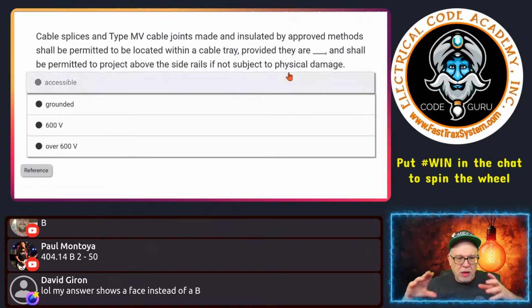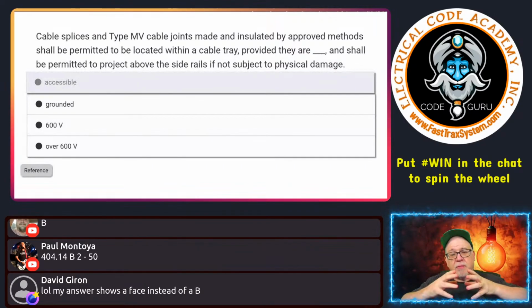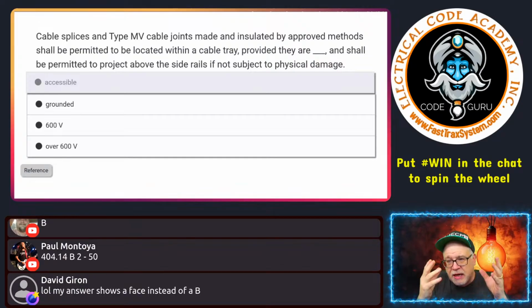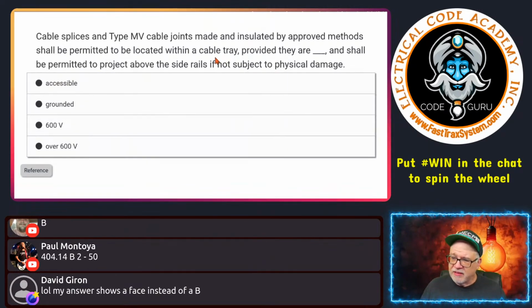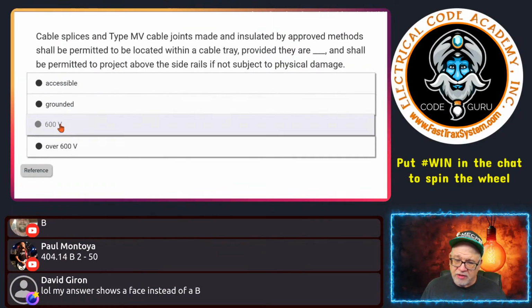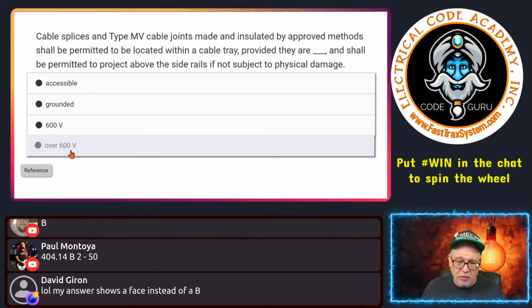to physical damage. So because of how they make the splices, they are allowed to protrude above the actual sidewall of the cable tray. Again, as long as they're not subject to any physical damage. And usually where these cable trays are installed, it's probably not going to be subject to any physical damage. But again, this is just saying you can. But here's the key. As it says, cable tray provided they are blank, accessible, grounded, 600 volts, or over 600 volts. Okay?